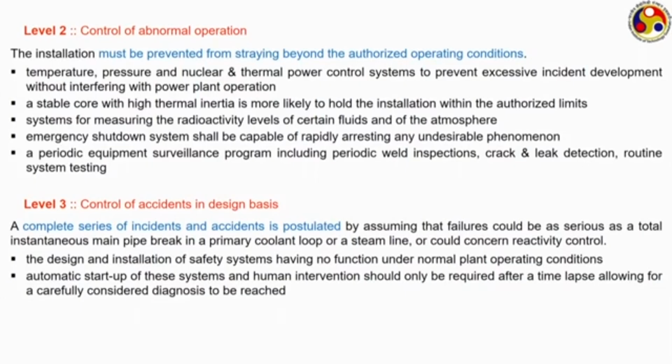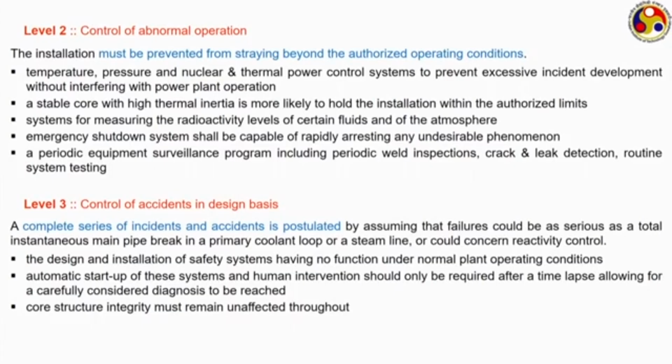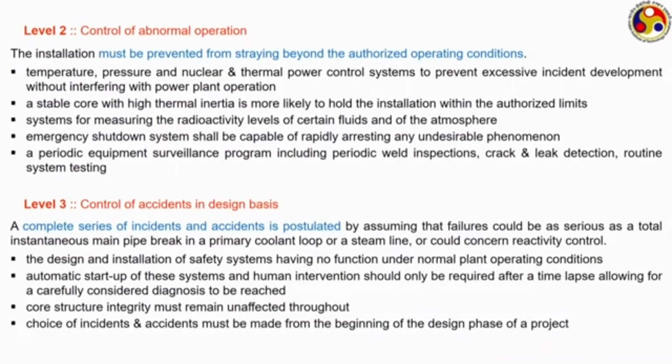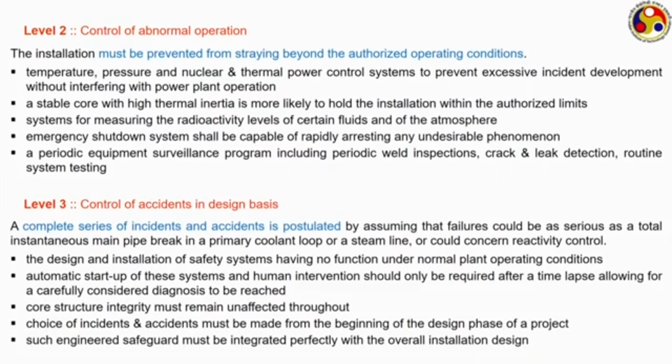Automatic startup of these systems is essential, and human intervention should be required only after a time gap, which will allow careful consideration so that a proper diagnosis can be reached. The core structure integrity must remain unaffected throughout, and the choice of incident and accident must be made from the beginning of the design phase of a project. Such engineered safeguards must be integrated perfectly with the overall installation design.